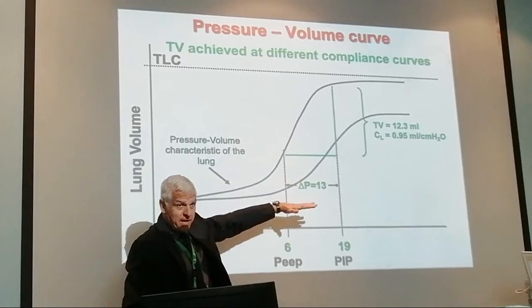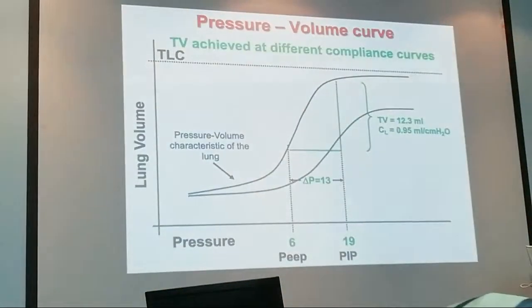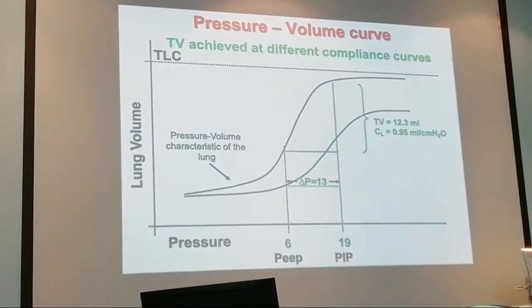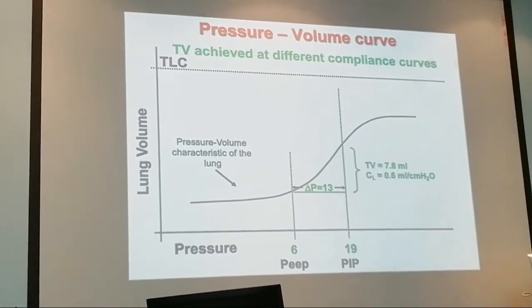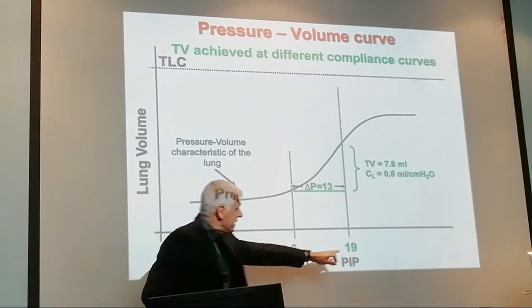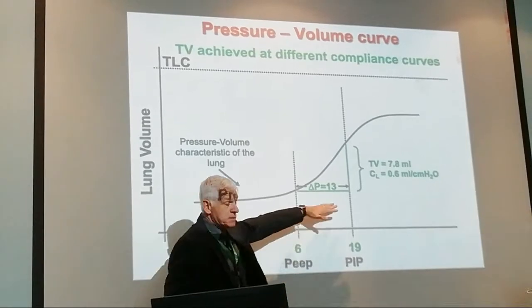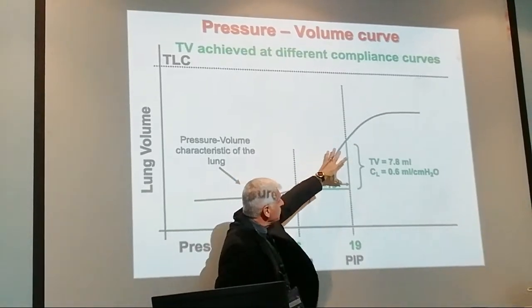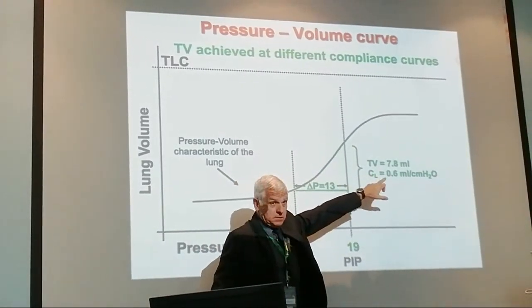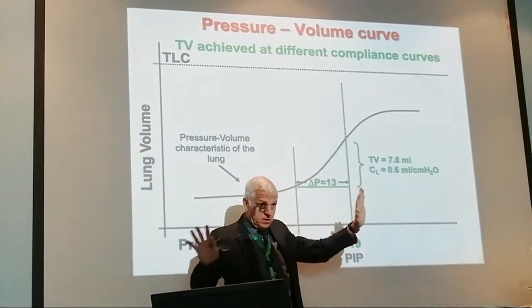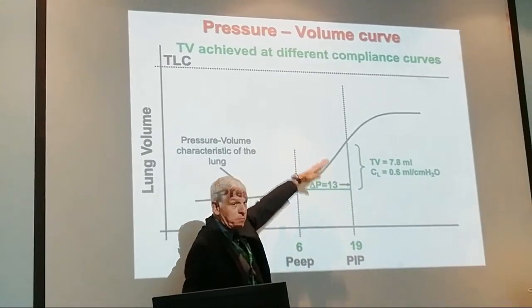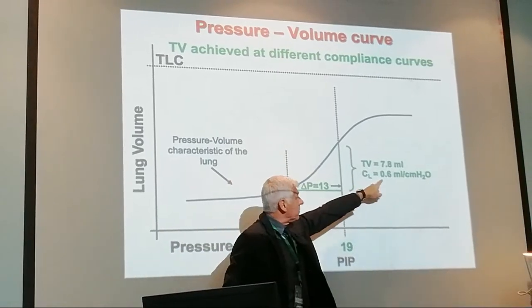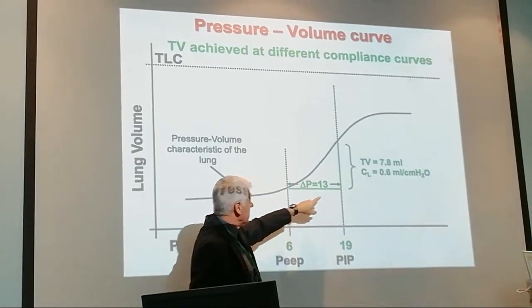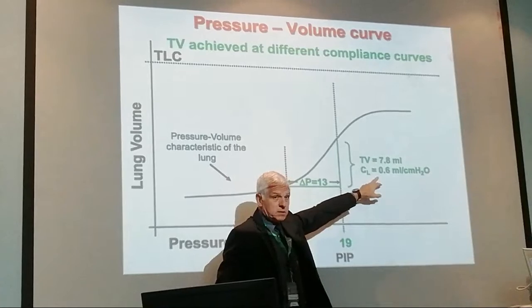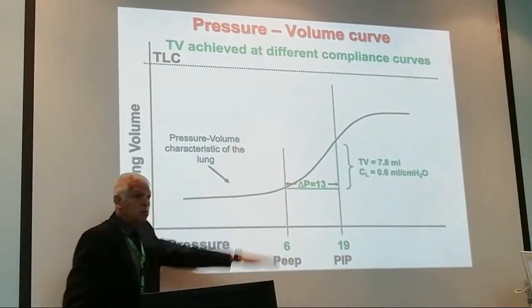So now the compliance curve went flat, and you haven't changed anything yet, so the ventilatory parameters are the same. With the same 19/6, your delta P is still 13, but now the volume you're getting is only 7.8. Same ventilator, nothing has changed. The only thing that changed was the compliance curve. Now your compliance is 7.8 divided by 13, which is only 0.6, and that confirms that compliance is worse.